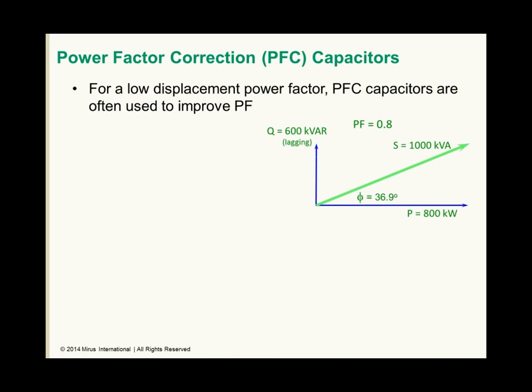Now, if we have a low power factor and that low power factor is a result of inductive reactive power, maybe from fixed speed motors or other inductive type loads, then we can apply power factor correction capacitors to improve it. In the example I'm showing on this slide, we again have 800 kilowatts of real power demand load. We have 600 kVAR of inductive loading requirement. The combination of the two vectors results in apparent power of 1,000 kVA, and this is indicative of a 0.8 power factor.